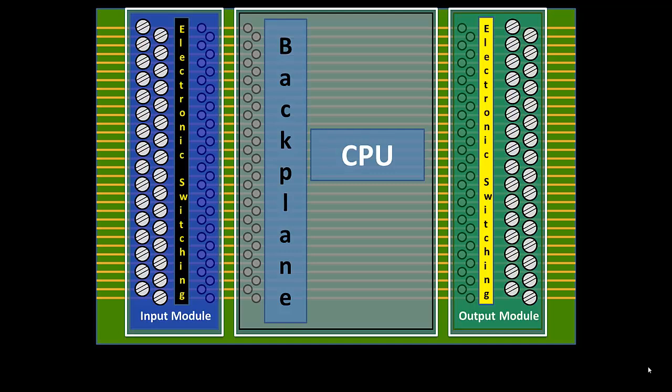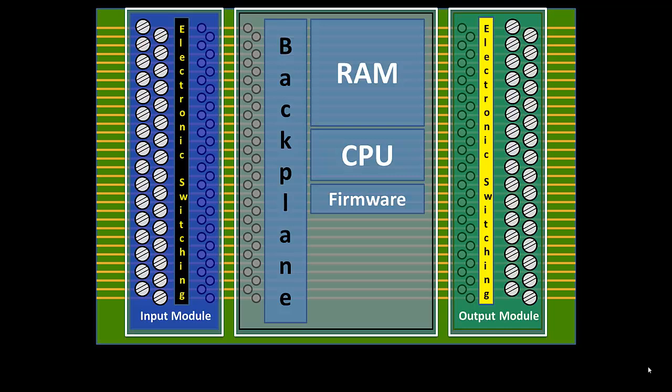Of course we need a brain — a central processing unit. The CPU is going to need RAM, random access memory, to store its list of instructions and to store the results from reading the input module. The processor will activate the input module, take the voltage states off the backplane, and store them as 0s and 1s in memory as a snapshot of the state of the input devices. The CPU also needs a guidebook to interpret instructions and retrieve features — we call this firmware.